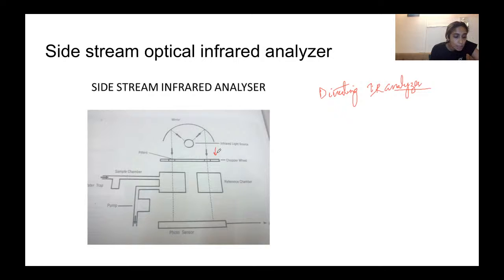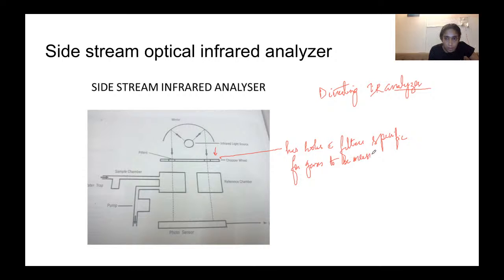The wheel has holes with filters specially selected for the gases to be measured. The gas to be measured is pumped continuously through a measuring chamber. The filtered and pulsed light is passed through the sample chamber and also through a reference chamber with no absorption characteristics. So the sample air enters here, and after passing through the filters, the light passes through the sample chamber as well as the reference chamber.